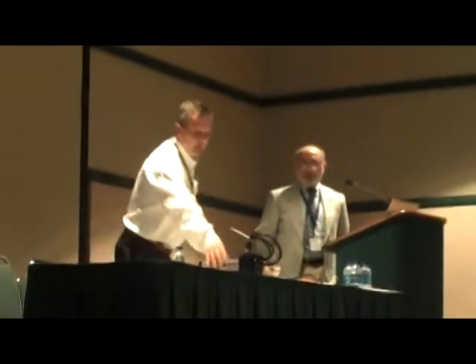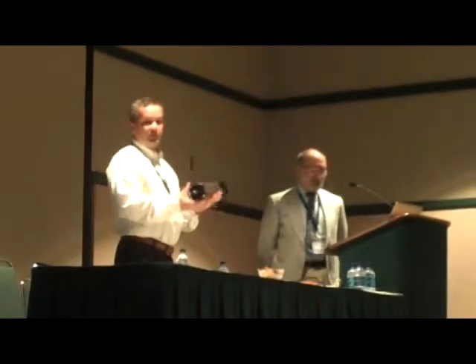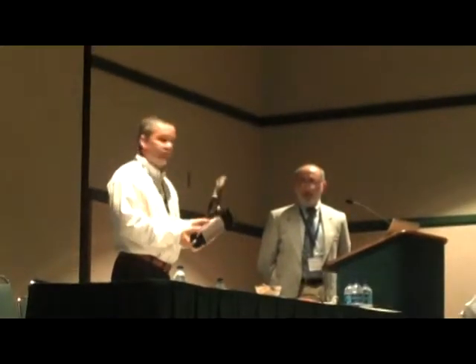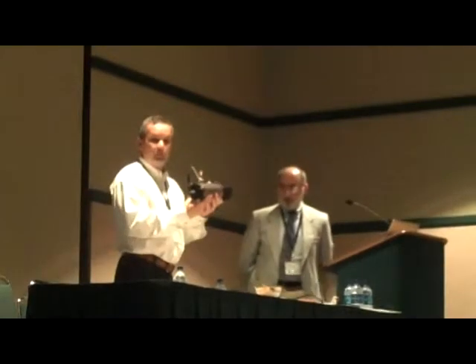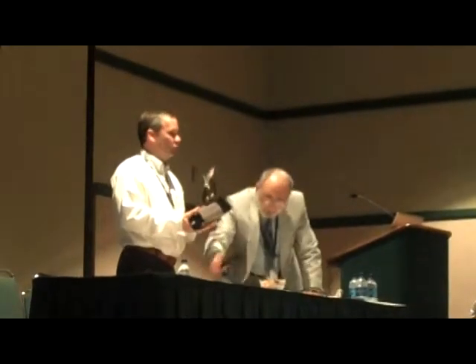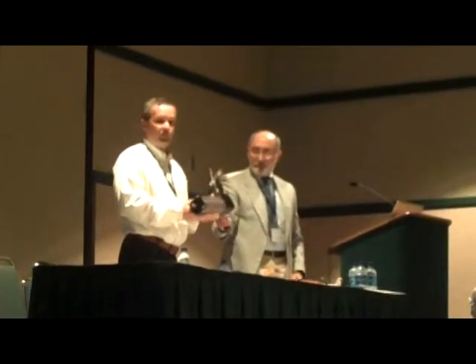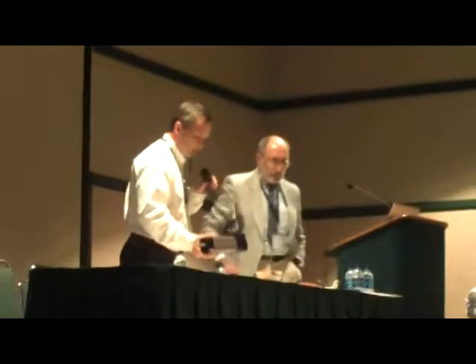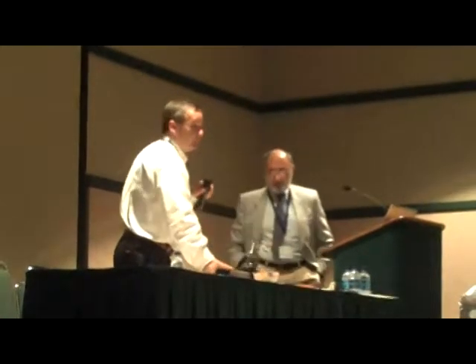One other thing, linear actuator. This is one size, which is a little bit larger than we actually need for that size. This will allow you electrically to vary the position of the control arm and totally automate and close the control loop, as we would say, based on either pressure, flow, or even maintain a constant speed if you needed to do that.